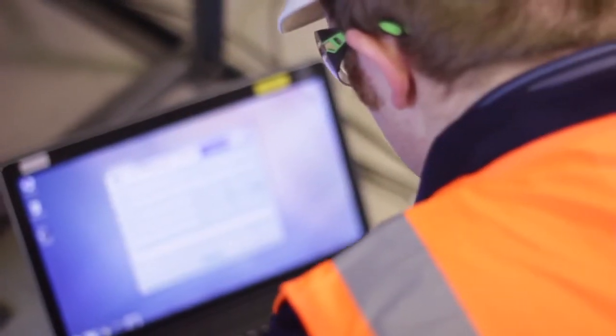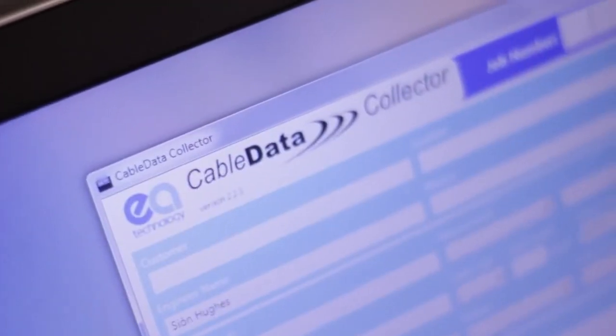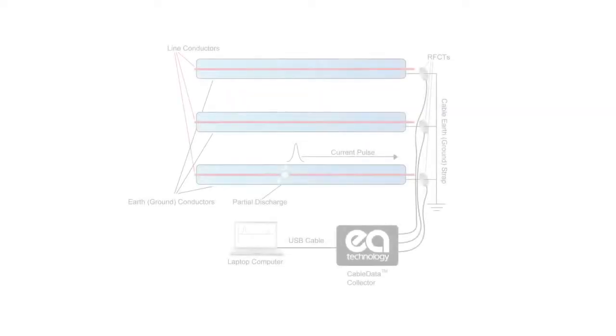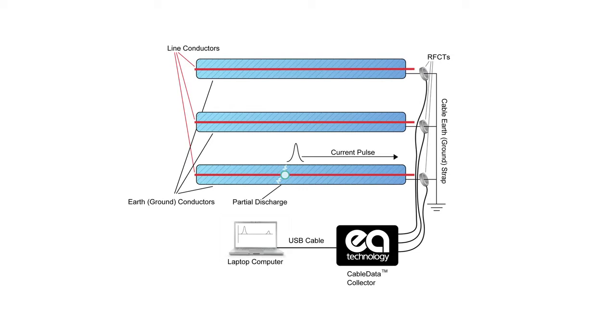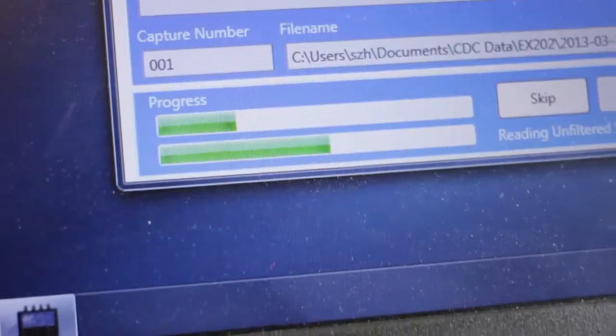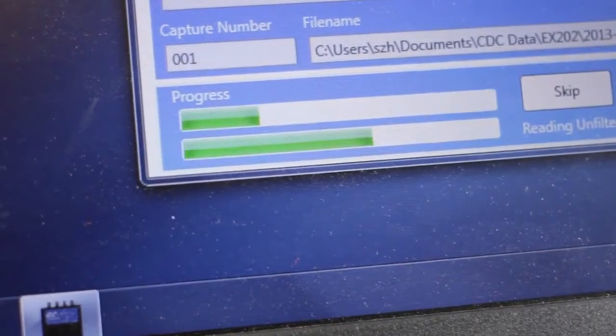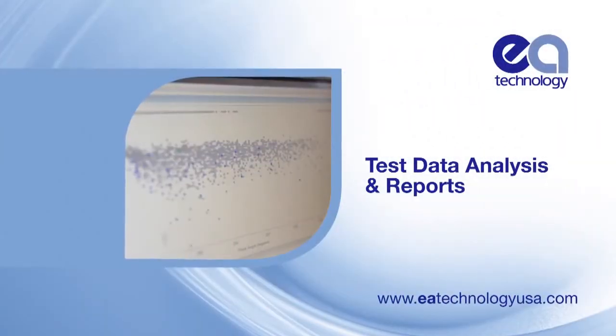To collect information about partial discharge activity, fire up the software that has been supplied to you on your laptop. As we showed earlier, the Cable Data Collector measures and records radio frequency currents in the range that is characteristic of partial discharge activity, and it does this in cables up to several miles in length. The screen will show when the data capture process is complete. Then, the file containing the results is ready for analysis.